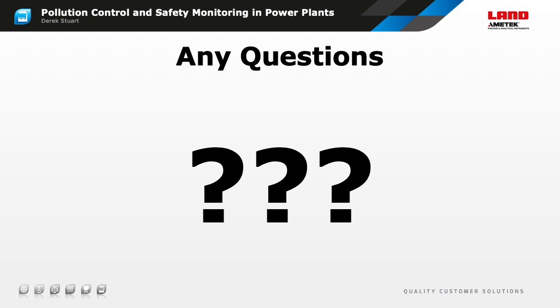Okay, another question for you here. What is the typical range of cost for a PM-CEMS, including both the initial capital and installation costs? Yeah, it can vary quite a lot. It depends on the manufacturer. It depends on the options selected. It depends on whether you're calibrating it as a PM-CEMS or an opacity monitor, which, for example, doesn't need the correlation test if you're reporting opacity as a percentage. But typically, as a starting point, if people are drawing up a budget, you probably want to start with a budget of around $25,000 US. You can shave a few options off that if you want to reduce the cost, and you can add some additional options to really get a fully featured system that has every option you could want. But that's a fairly reasonable starting point.